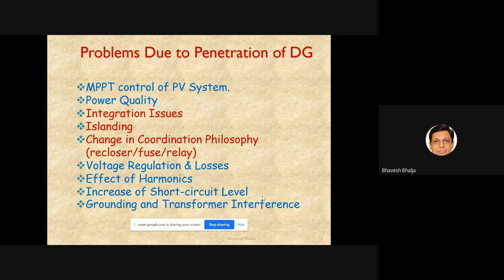An electrical island is a phenomenon in which a small portion of the power system network is disconnected from the grid, and in that small portion you have local distributed generators installed, which, depending upon their capacity, supply power to the local loads available in that small island. That is nothing but an electrical island.